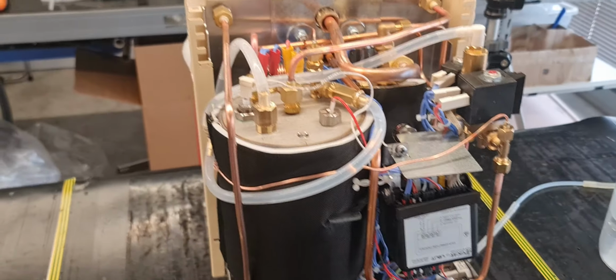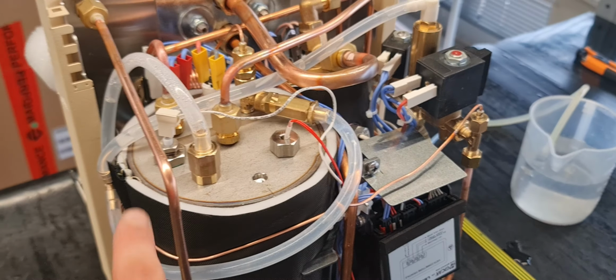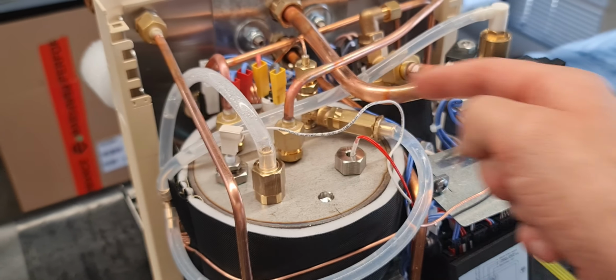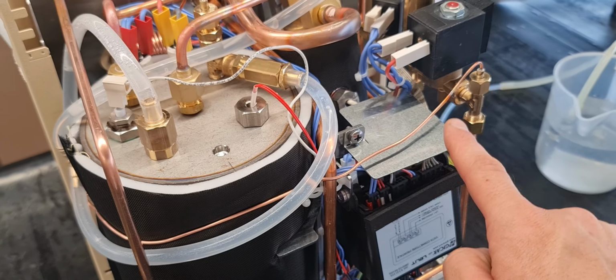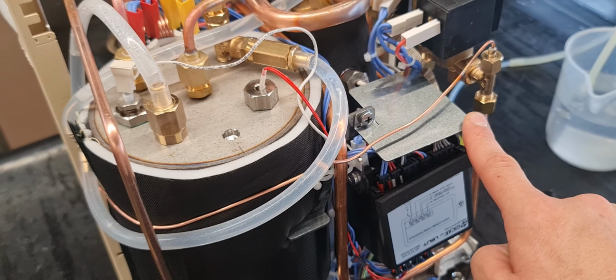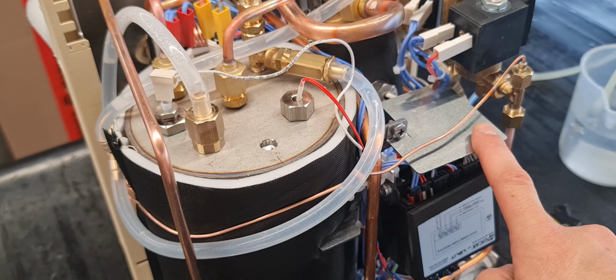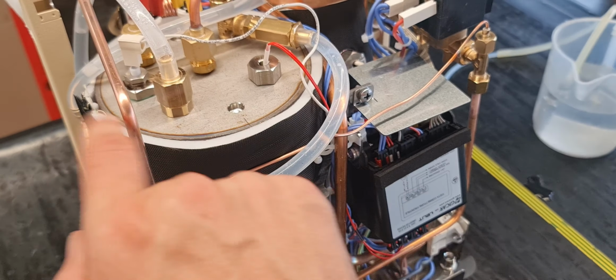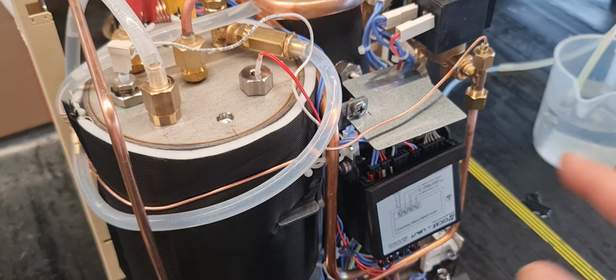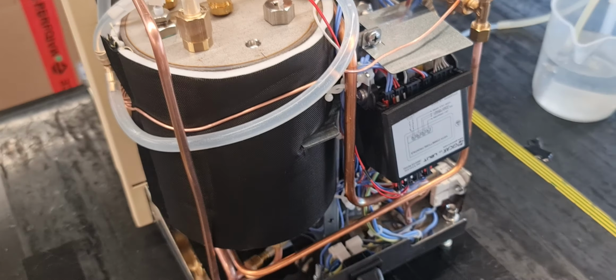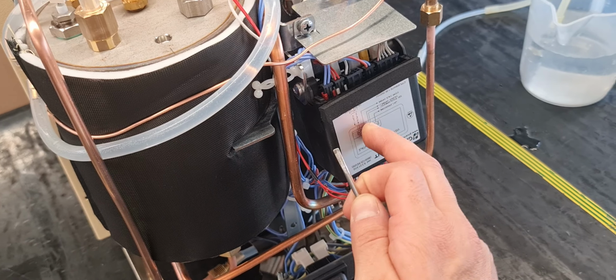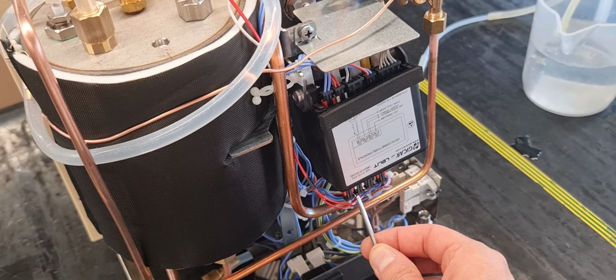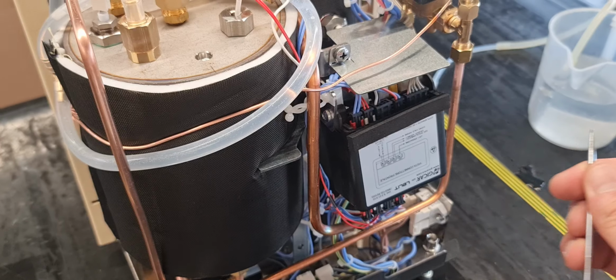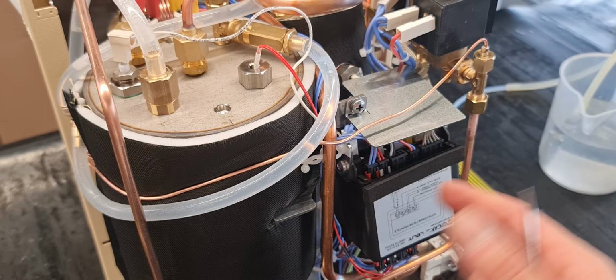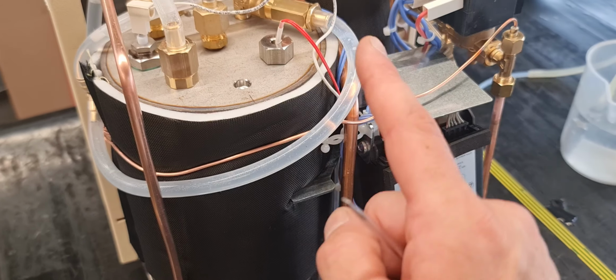But we have to do this test to understand where the problem is. Or is it the water level probe, and you have to do the test to connect this one in another place. If you put this one in contact to the land and the machine stops refilling, it means that the wiring works, you have a problem on the water level probe. In the other case, if you do this test, put into contact the board, and the refilling does not stop, it means that you have a problem here. But if you put this one, the jumper, and the machine stops the refilling, it means that this one works, and you have to check the wiring.